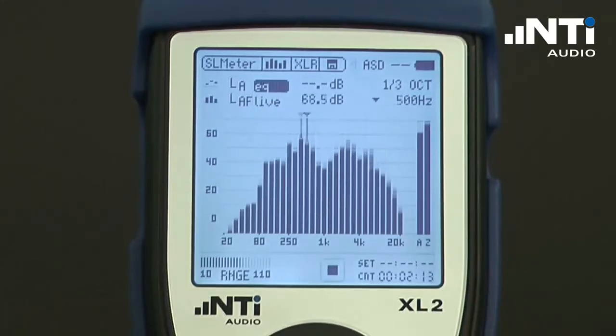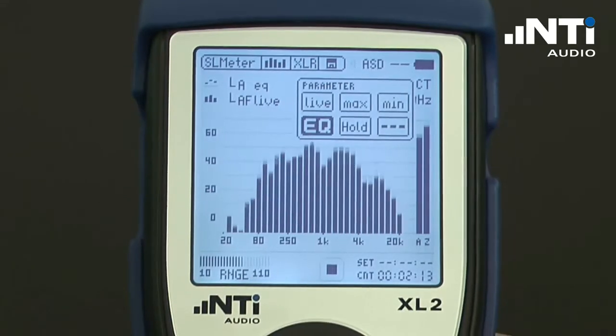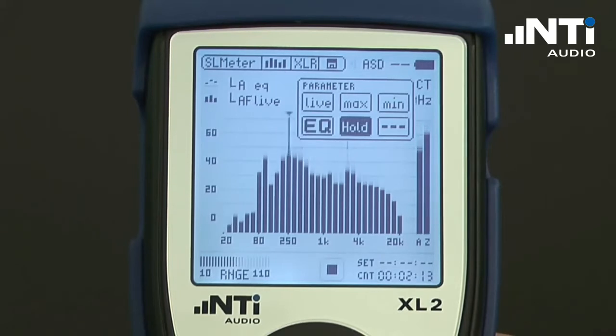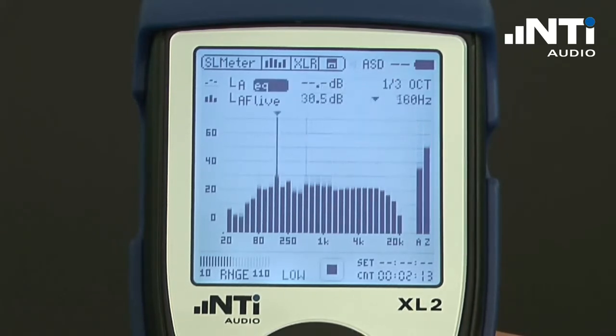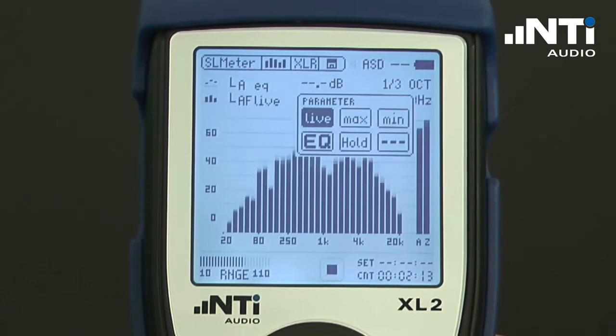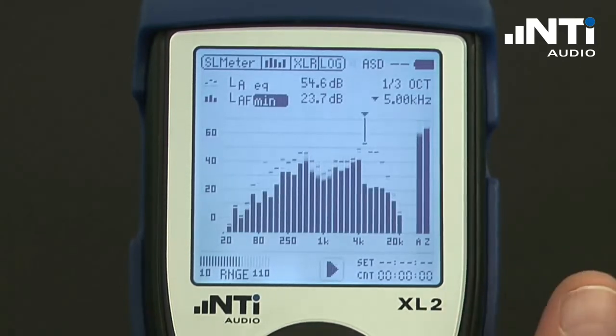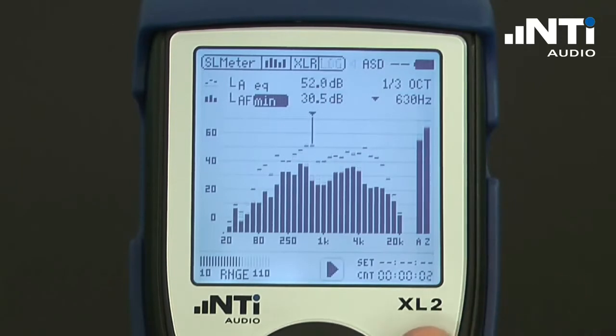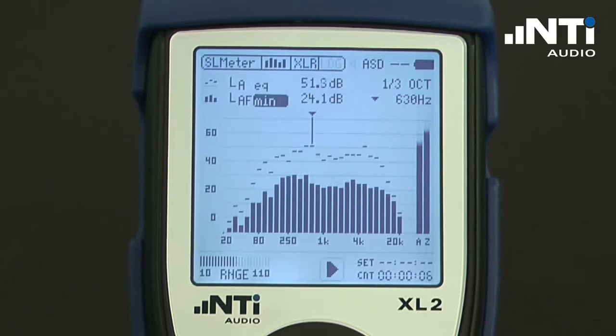We may select which trace we want to have displayed — it can be live, max, min, EQ, or a hold for a specific period of time. The same applies for the bar trace, which is currently live and can be switched over to, for example, minimum. As soon as we start the measurement period, we see dotted lines for EQ, and the minimum is represented by the bars.